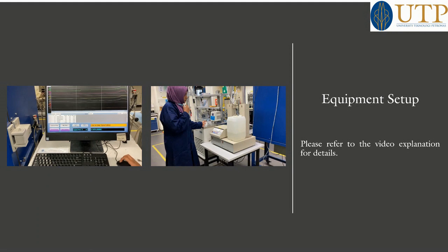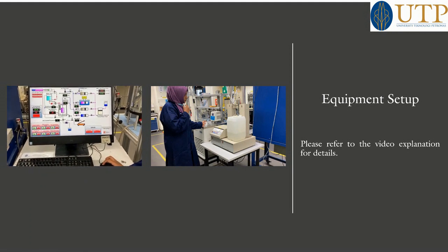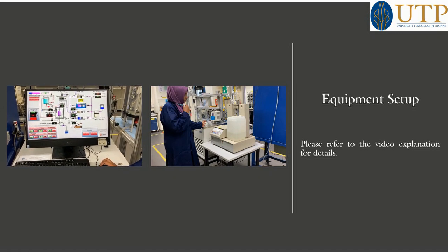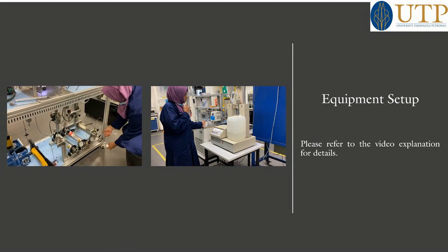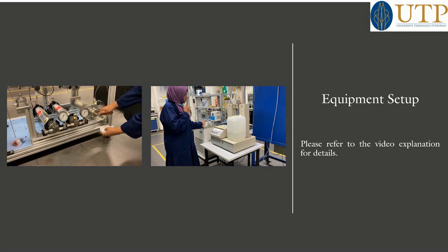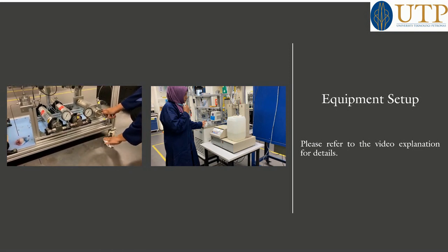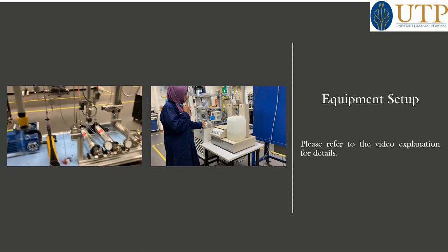Now we are going to the main page. All the pressures have decreased, but there is still some pressure inside my water accumulator and oil accumulator. So open this one. When you open this one, the fluid is coming out and you will see the pressure is already less, 14 and 3.